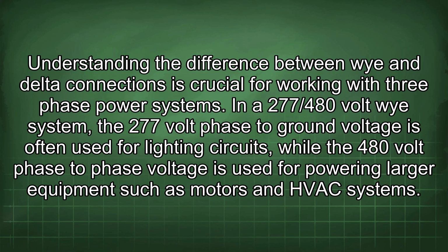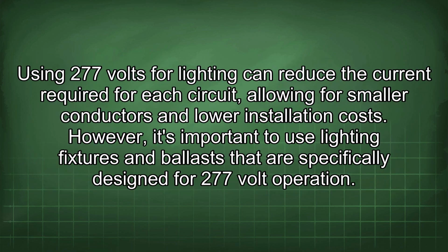In a 277/480 volt Y system, the 277 volt phase-to-ground voltage is often used for lighting circuits, while the 480 volt phase-to-phase voltage is used for powering larger equipment such as motors and HVAC systems. Using 277 volts for lighting can reduce the current required for each circuit, allowing for smaller conductors and lower installation costs. However, it's important to use lighting fixtures and ballasts that are specifically designed for 277 volt operation.